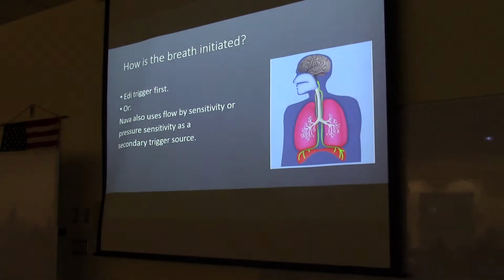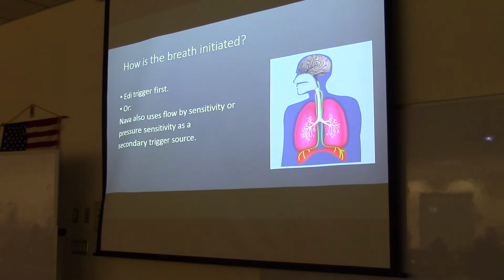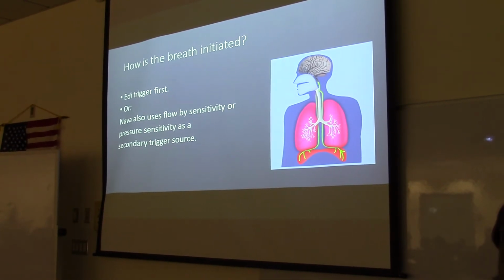All right, so the ventilator is waiting for the trigger to be hit, but there's also a backup in case. What happens if that NG tube is displaced? Does the patient not get ventilated? So the ventilator will look for more than just the signal from the EDI catheter. It'll also initiate a breath if flow-by is sensed, the flow-by trigger or pressure trigger, as a secondary trigger source. That sounds safe, doesn't it?